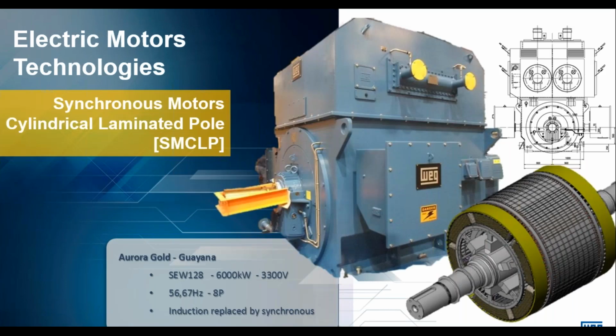Right, then we get to the synchronous motor technologies, the first of which is the cylindrical laminated pole. This is arguably the most versatile and fit for purpose synchronous type, if a synchronous motor is required for an application. So it would make sense from our perspective to first analyze if you can utilize a cylindrical synchronous machine, a cylindrical laminated pole design, before you start looking at other designs, since this construction is the most simple to manufacture and gives some additional advantages.